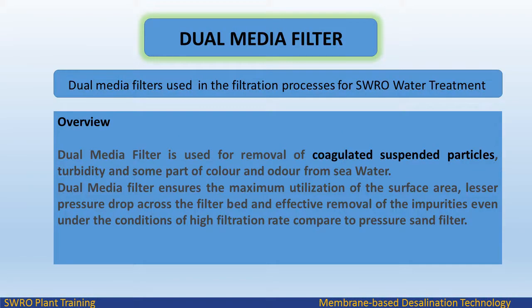Dual media filters are used in the filtration processes for seawater and water treatment. The dual media filter is used for removal of coagulated suspended particles, turbidity, and some part of colour and odour from seawater. It ensures maximum utilisation of the surface area, lesser pressure drop across the filter bed, and effective removal of impurities even under conditions of high filtration rate compared to pressure sand filter.